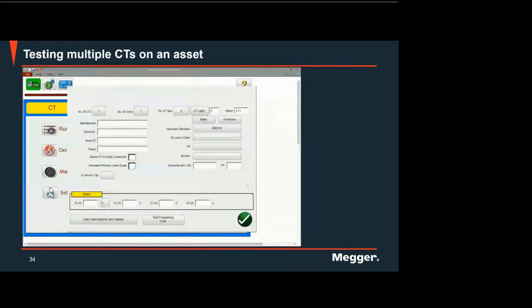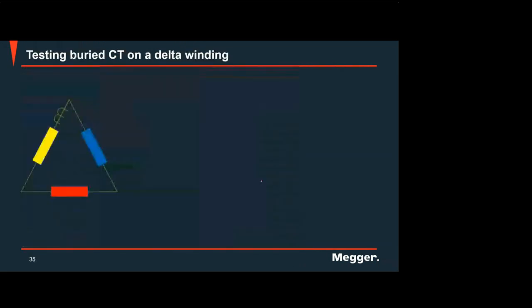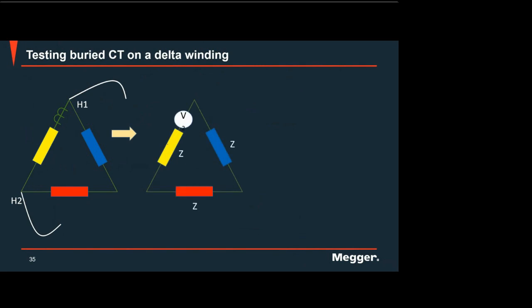So like I've said, you can test multiple CTs, and also you can test buried CTs, or the bushing CTs. Those are buried CTs. So you can test buried CTs on a delta winding. So you can put H1. For example, this is your transformer and you have a CT inside. Then you can connect the H1 and H2. Of course, you are measuring the voltage here. So you have the factor of 2/3, right? So voltage measured is equal to 2/3 of the voltage V2.